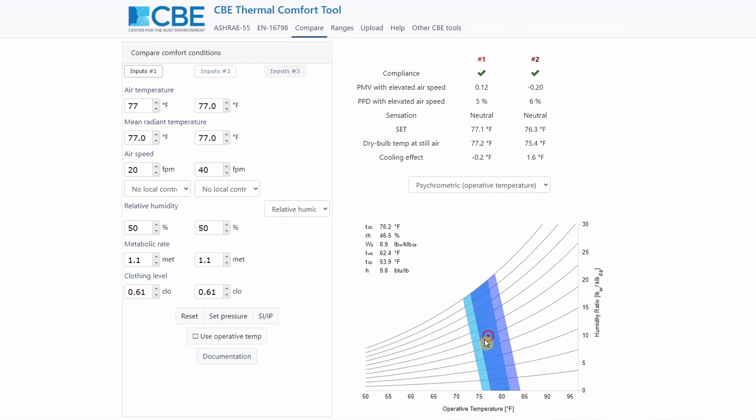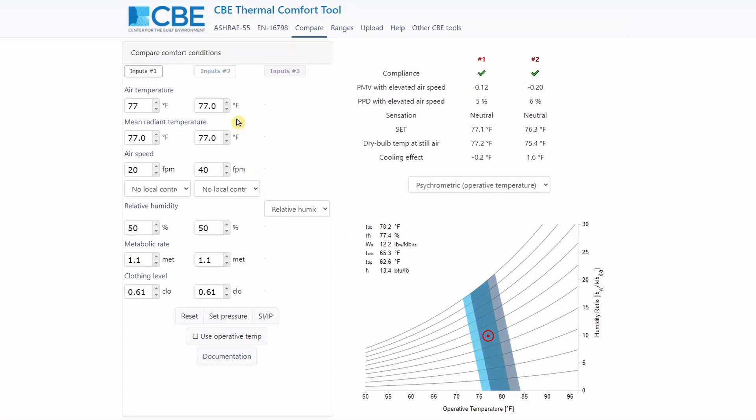As you can see from this chart here, by increasing the airspeed, we can slightly move to the right side the thermal comfort region. What does it mean? It means that if all the other conditions are equal, but only the airspeed changes, people will perceive that higher temperatures are as comfortable as lower temperature when the airspeed is lower.